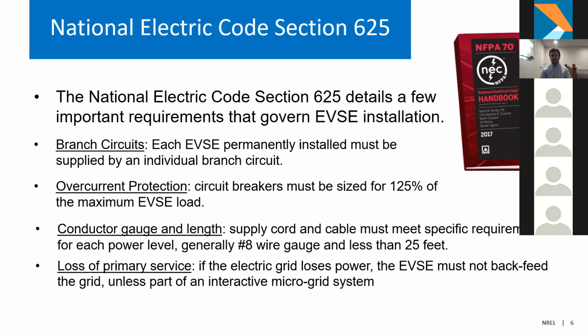And then beyond that, there is a loss of primary service. So if the electric grid loses power, this is a little bit more of a higher level or futuristic requirement, but in the event that the EVSE happens to have, say, a vehicle to grid or can have bidirectional charging, if the grid loses power, the EVSE is not allowed to backfeed the grid or provide electricity to the grid when there is an outage. Next slide.